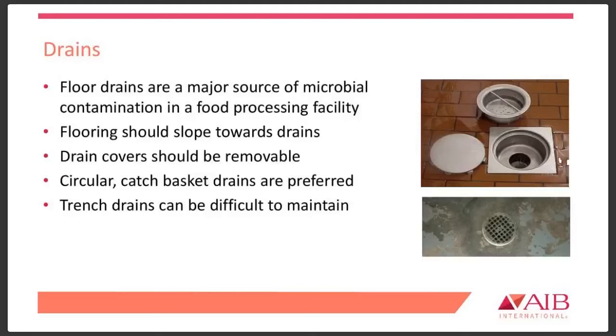Circular one-piece stainless steel drains with catch baskets are preferred, as they can be easily serviced. Trench drains, on the other hand, can be a bit more difficult to maintain due to the increased surface area, as well as issues with the grouting and sealing of the trench drains. There also could be an issue during sanitation, as personnel may incidentally hit it with high pressure water and cause the aerosolization of bacteria. So if trench drains are going to be used in the process, it's really important to limit their depth to allow for effective cleaning, and that they be adequately sloped to prevent standing water.